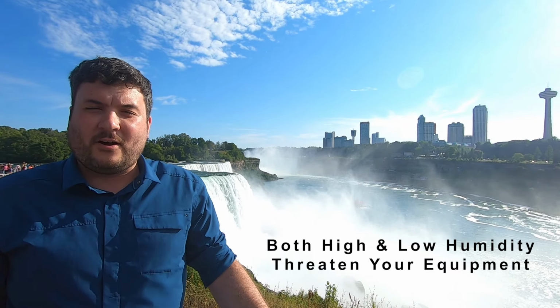to any unprotected electronics. Most people recognize that, but you may not also realize that low humidity is also a danger because you can have a buildup of static electricity, and when that discharges, you can have damage to your electronics. So humidity is probably the most important environmental you need to monitor aside from temperature. And it's very easy to do.